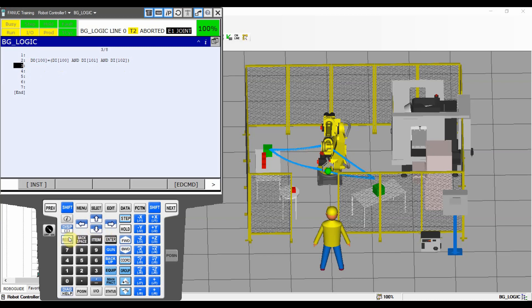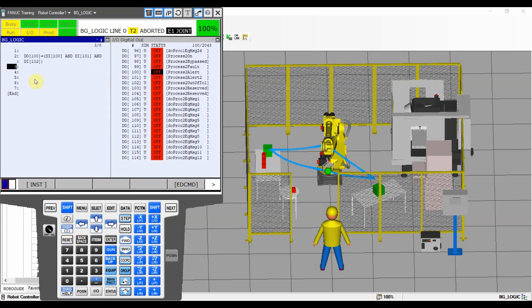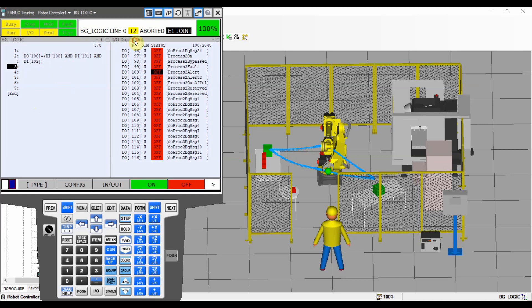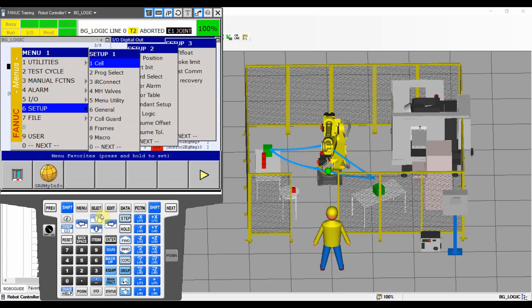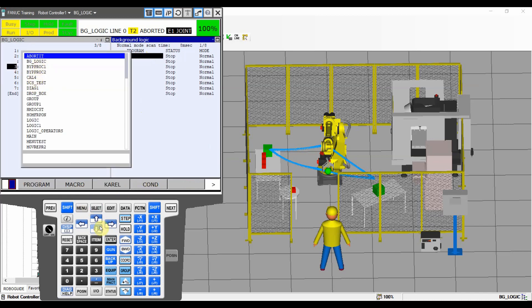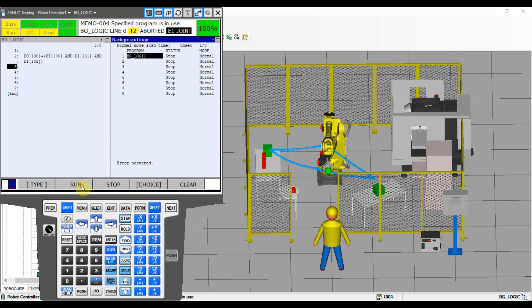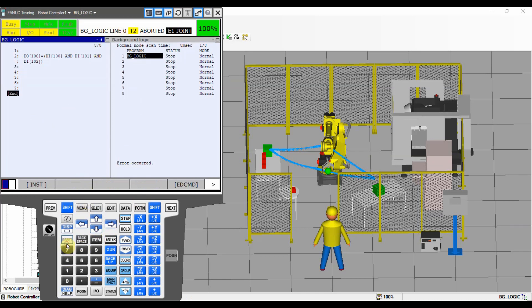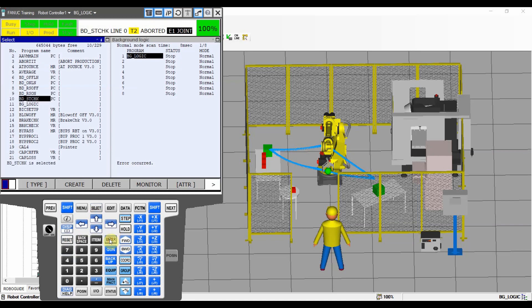One thing to remember when selecting the background logic: the program cannot already be running in the background when you're making changes, and you also can't have it open when you try to enable it. I have the program selected now — let me show you the error you'll see. If you go to background logic and try to choose and start the program, it will say there is an error and that the specified program is in use. Simply select a different program, go back, hit Run, and it will be running.